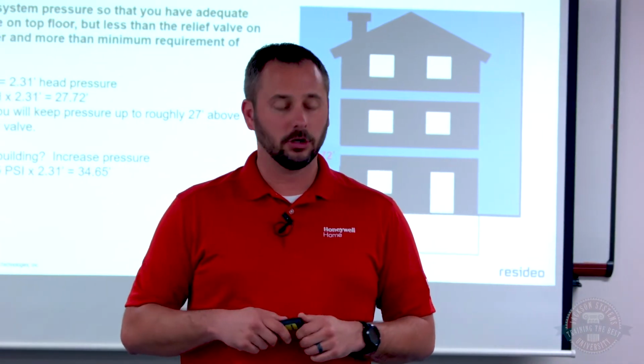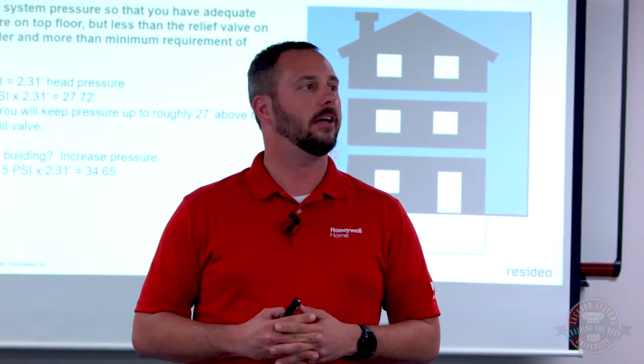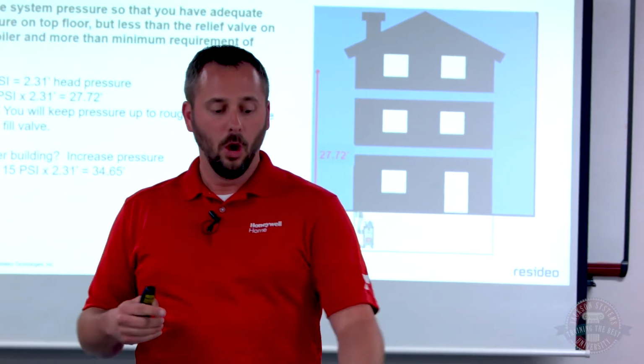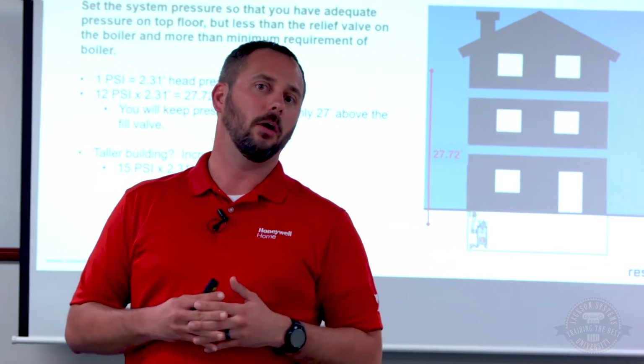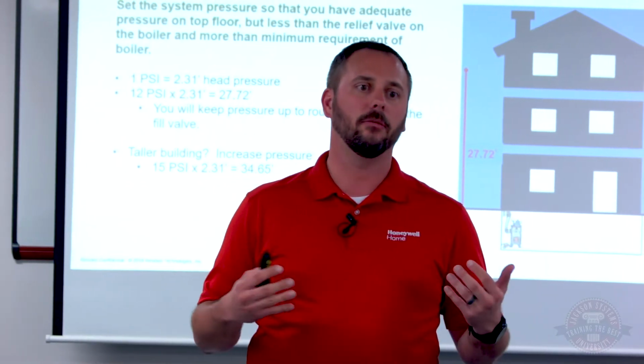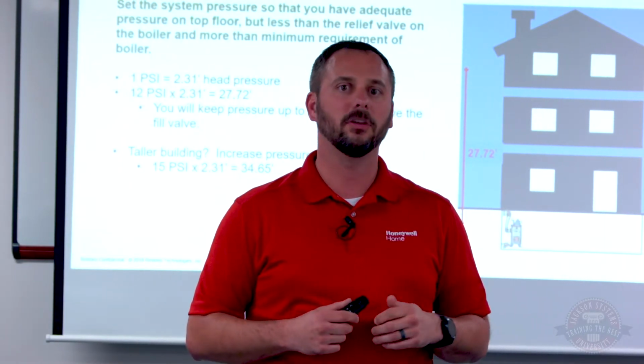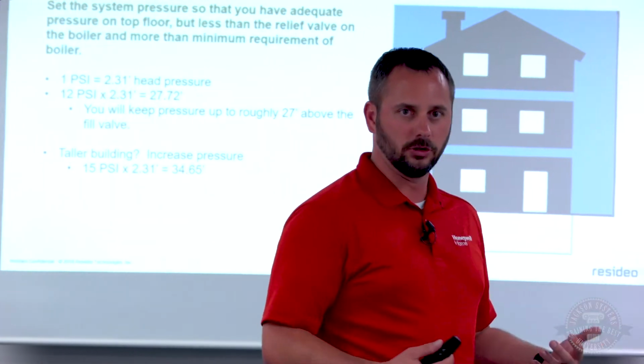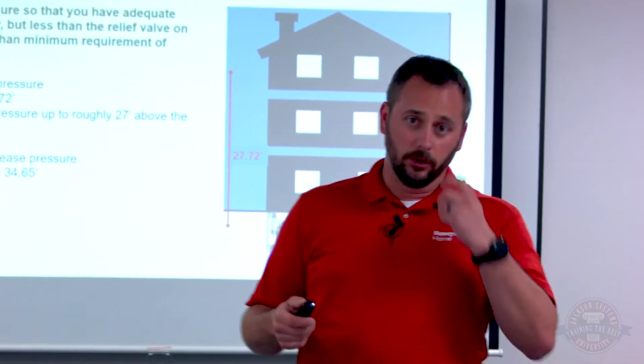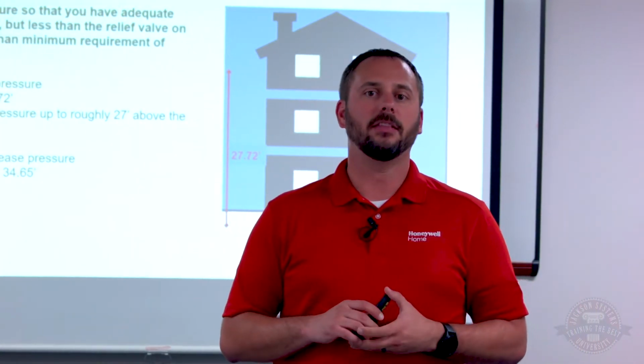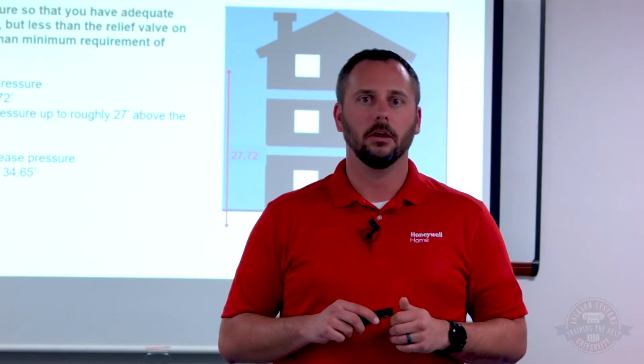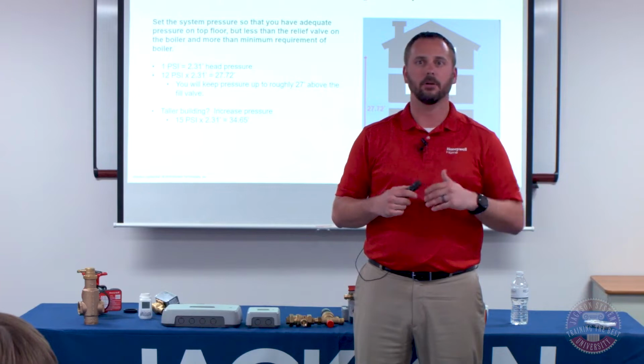So anyways, with the pressure, you basically just need to make sure you've got the capacity down at the basement to handle that. Let's say we've got a really tall building. Something to keep in mind, and this isn't real common in residential systems, but sometimes in light commercial jobs: if the boiler is in the basement, you may have to set that pressure incredibly high to get the capacity of height. So you'll have pressure at the top. It could be a radiator, in-floor heating, whatever it is.